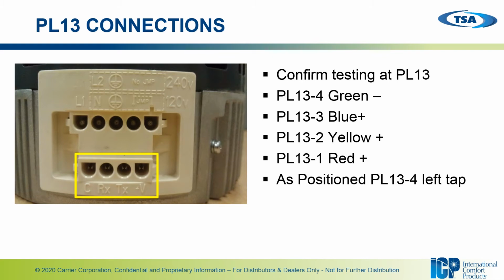On the motor, your control connections are going to be listed as C for common, RX, which is used to designate a receive command or receive signal, TX, which is designating transmit signal, and then you have a voltage. Okay, that's going to be your 12 volt supply voltage to the motor. And you could check for all of those at the motor as well as the control board.